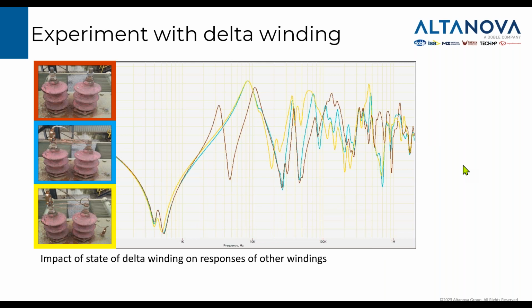And I once made a simulation of this effect on another transformer. This one was in Ireland. I had a three winding transformer, which again had the tertiary winding grounded in one corner. But this time, that corner was brought to the tank. So we had two bushings, normally in service, closed to close the delta and grounded to this point here.